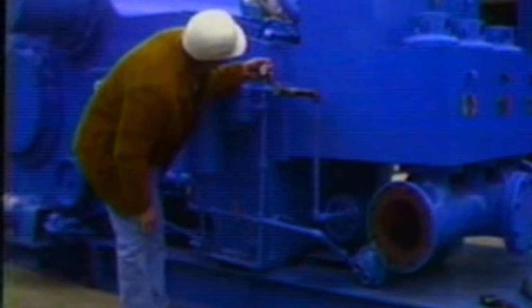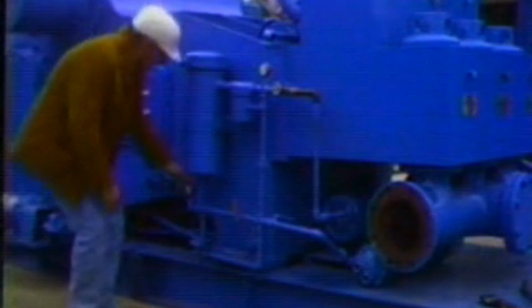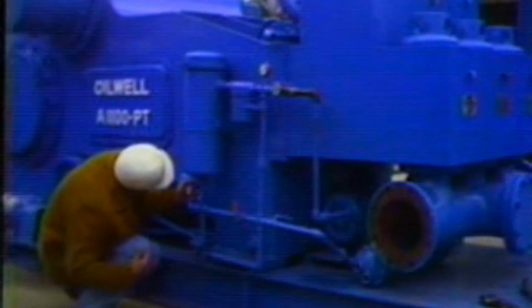Be sure to watch the pressure gauges to make sure that oil is circulating. Now stop the pump and let the oil settle for a few minutes. Now is a great time to recheck the extension rod clamps for tightness. Then check the oil level and add or drain some oil if you find it necessary. You've taken pretty good care of that pump. Now she's back in business and she'll serve you well.